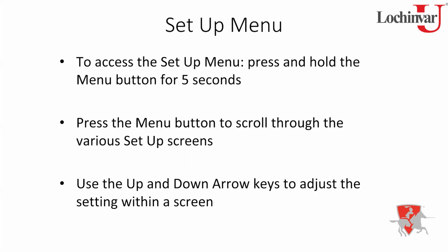Now, there are two menus within the control. You have what's referred to as a setup menu and then the service menu. The setup menu is going to be our adjustable programming items. The service menu is basically just information telling us what's going on with it. So to get into the setup menu, just press and hold that menu button for 5 seconds. Once you do that, you're going to go into the first parameter. Now to scroll through the various parameters, you're going to press that menu button, and keep tapping it to roll through your various adjustable items. If you land on something you want to make an adjustment on, use the up and down arrow keys.